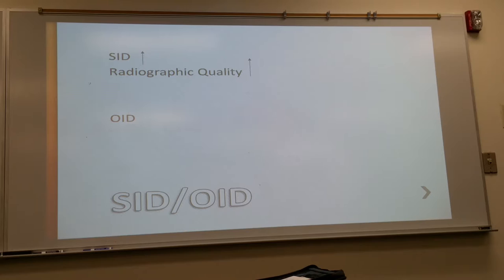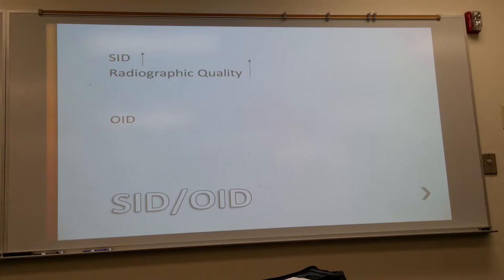So there will be a reason for some of this. Your technical factors are typically set at a 40 inch SID. But you'll go to hospitals and they may use 44 inches as their standard instead of 40 inches. Mammograms, their standard SID is 36 inches. So 40 is give or take. You're not married to that. You can change whatever distance you want to use.